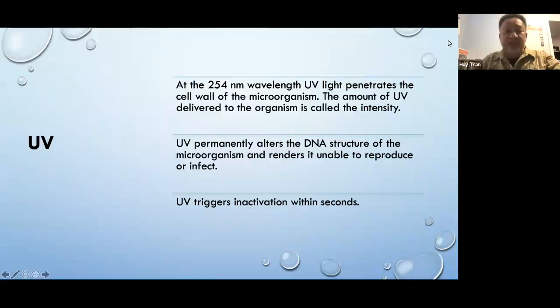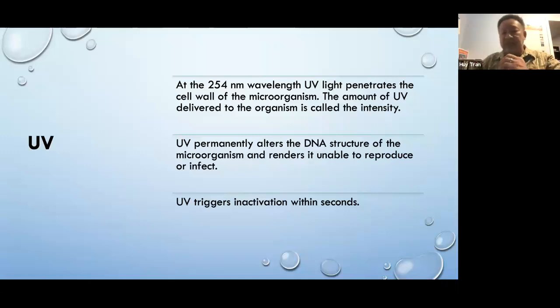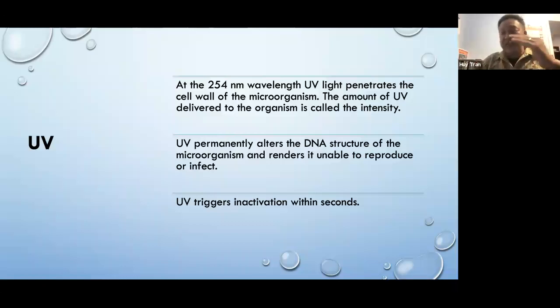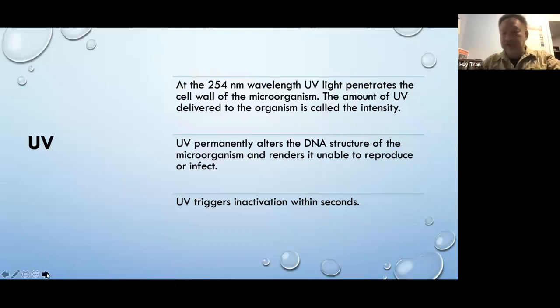UV is also very commonly used, but many people say it doesn't work — the problem is usually that the water isn't clear enough. UV is a light, so there must be good transmittance in the water for it to work effectively. If water has coloring or fine particles, those particles cast shadows and anything in that shadow remains living. You should have a transmittance rate of 90% or better; discuss this with your UV manufacturer when sizing.